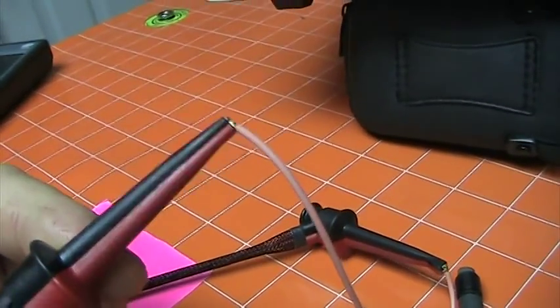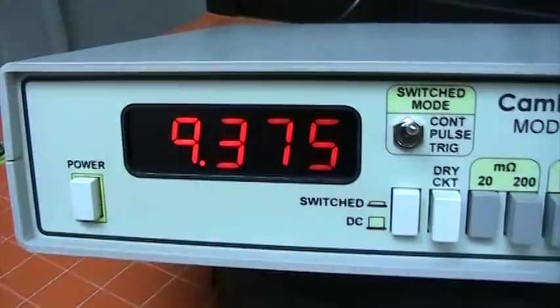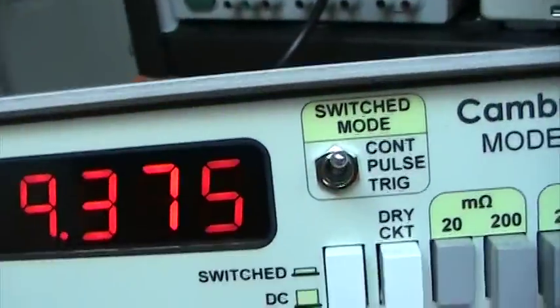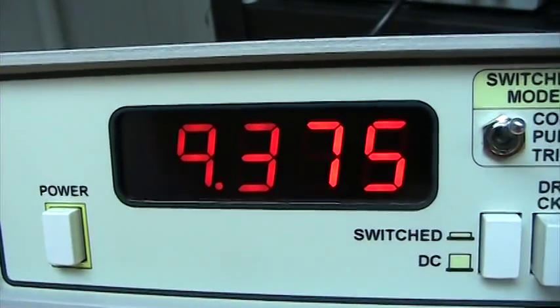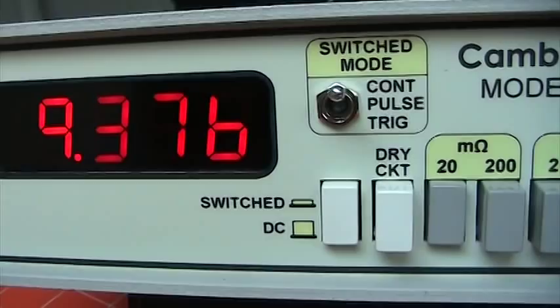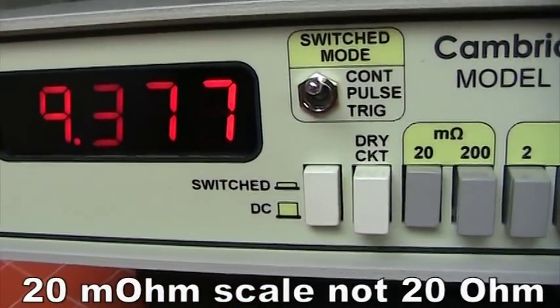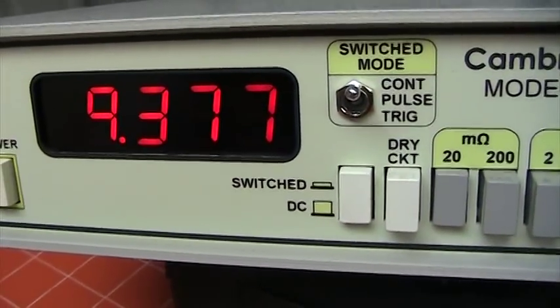So you've got your sense lead in between your current leads. The meter is reading 9.375 milliohms. We're on the 20 milliohm scale, and we are on switched DC, which means it's taking a reading every 666 milliseconds.